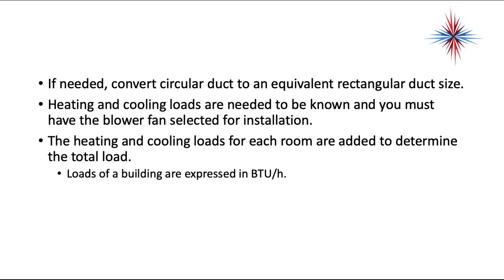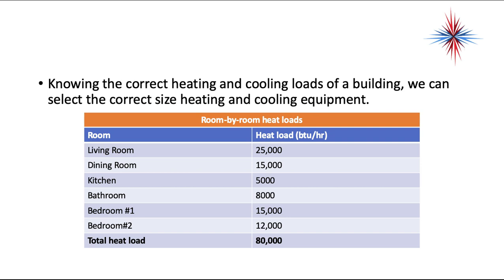If needed, convert circular duct to an equivalent rectangular duct size. Heating and cooling loads must be known, and you must have the blower fan selected for the installation — you have to know how much air, at what pressure, and at what speed you're going to get it. The heating and cooling loads for each room are added to determine the total load, expressed in BTUs per hour.